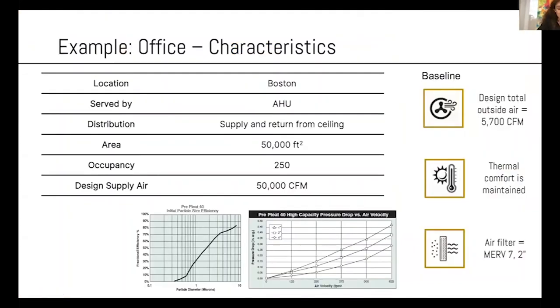So let me show you an example. Here I have an office building in Boston, 50,000 square feet, 250 people. They have the minimum outside air per ASHRAE standard 62.1, and they have a MERV 7, 2-inch filter. And remember what I told you about the filter that you can get? This is an example of efficiency and pressure drop. So pressure drop versus airflow for different depths.